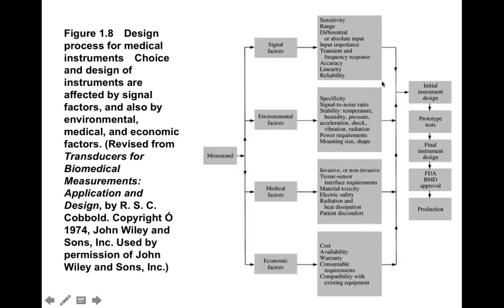So taking all these factors into consideration, typically you'll come up with some kind of initial instrument design. Then from there, you'll do some testing with a prototype, then some final design, an approval from the FDA, and then production.